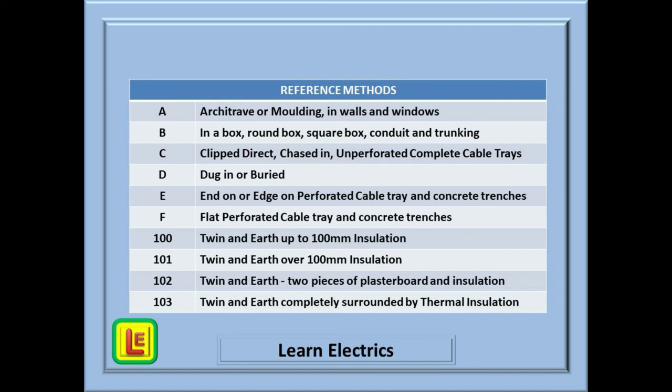And there we have it. Our 10 simple reference methods. A for architrave or in building materials, walls and window frames. B for round box or square box in conduit or trunking. C is clipped direct to the wall or chased into the wall, or for non-perforated complete cable trays. D was for dug in, buried in the ground. E was for the perforated cable tray, on end or on edge. And F was for flat perforated cable tray. Remember that concrete trenches are also E and F. When we looked at twin and earth cables, we used 100 for loft insulation up to 100 millimeters thick. 101 was for insulation over 100 millimeters. 102 saw two sides of plasterboard. And 103 was our worst case where the cable is completely surrounded by thermal insulation.